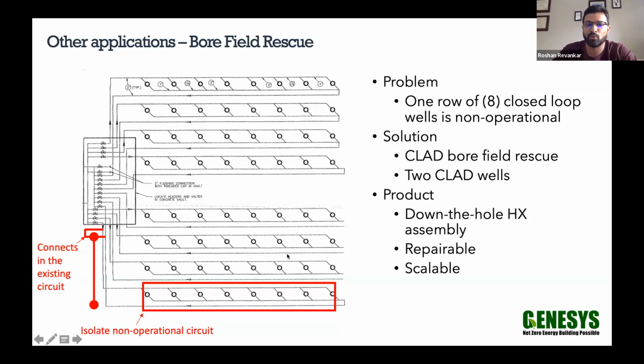They've been seeing groundwater, their borehole entering water temperatures creep up in the high 90s and even surpass 100. But it's a facility that's already up and running and sees high traffic. They don't want to be drilling another 8 boreholes or 16 boreholes and approached us for a solution. We are going in with 2 CLAD units, so essentially drilling 2 boreholes. And all we are doing is connecting.